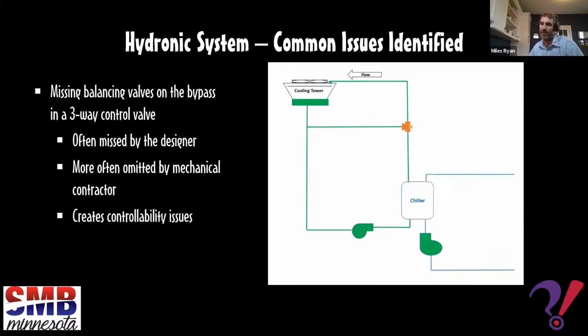One other example of this: if you have a cooling tower and cold weather operations, and you have a bypass with a 3-way diverting valve, which is very common, in this bypass leg you also have to have a balancing valve. I almost never see it, and it definitely creates issues. However, most people don't witness this issue until you get to cold weather operations, because that's when this valve starts modulating, and that's when the system can get really unstable.